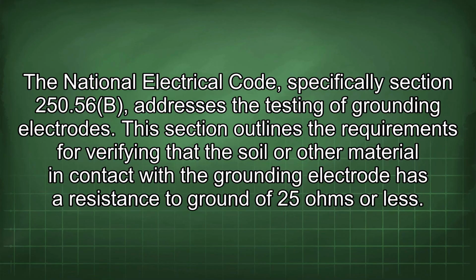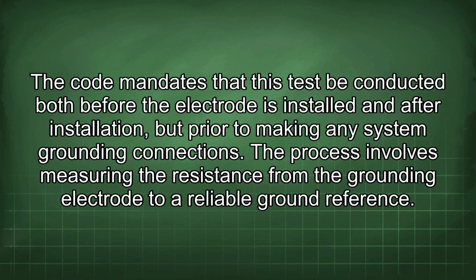The National Electrical Code, specifically Section 250.56(B), addresses the testing of grounding electrodes. This section outlines the requirements for verifying that the soil or other material in contact with the grounding electrode has a resistance to ground of 25 ohms or less. The code mandates that this test be conducted both before the electrode is installed and after installation, but prior to making any system grounding connections.